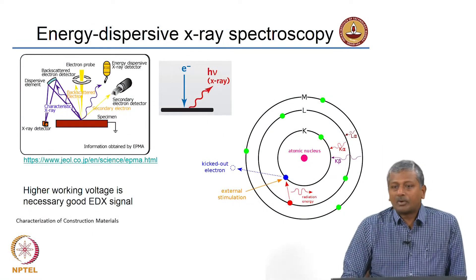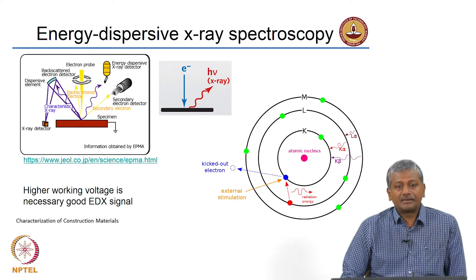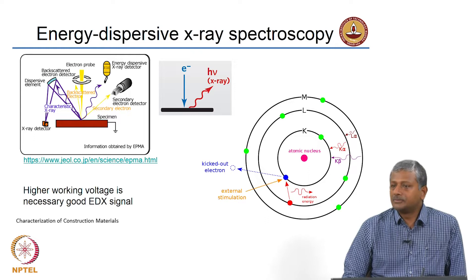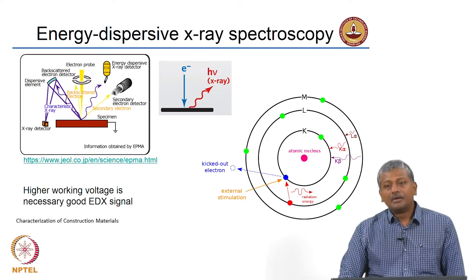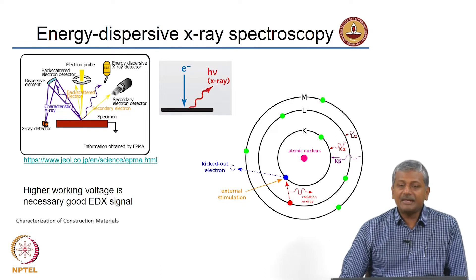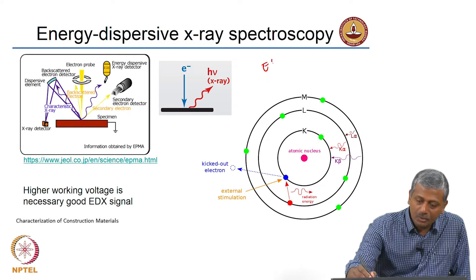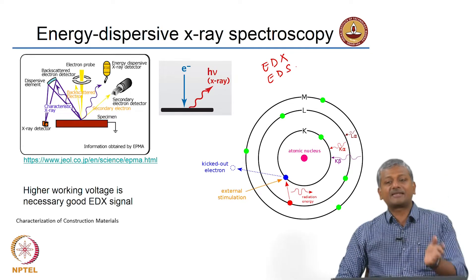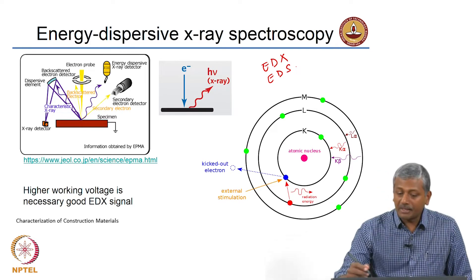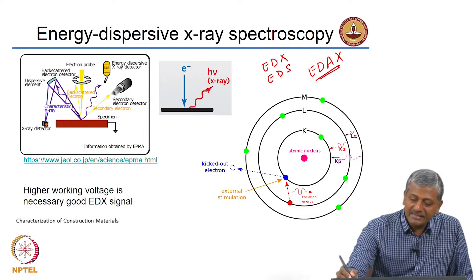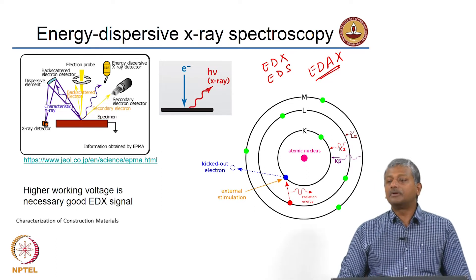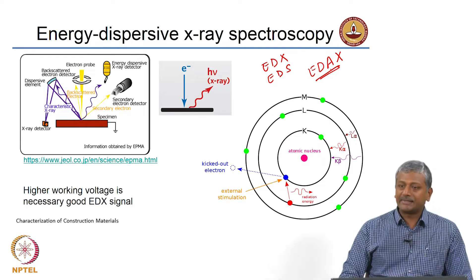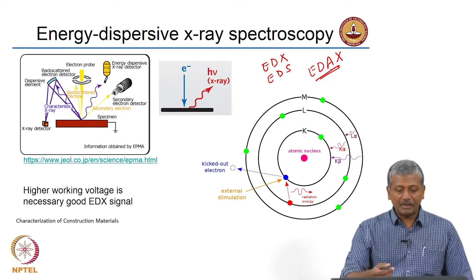An important concept in SEM is the presence — not always — of an X-ray detector. Basic SEMs have only the secondary detector. For an extra cost you can get the backscattered detector, and you can also invest in an EDS or EDX detector — energy dispersive X-ray analysis or energy dispersive spectroscopy. Sometimes people wrongly call it EDAX, but EDAX is a commercial product name. When writing papers, use the scientific name: EDX or EDS.